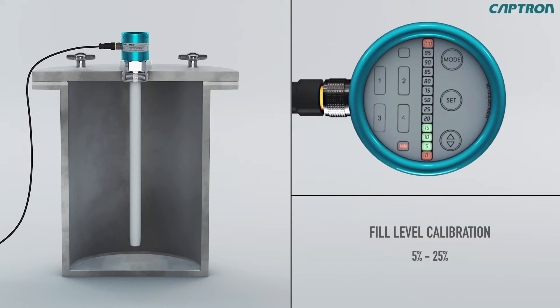Fill the tank with 5 to 25% of the desired measurement range. Now with up-down you can set the value which corresponds to the actual fill level. Then confirm the value with set.